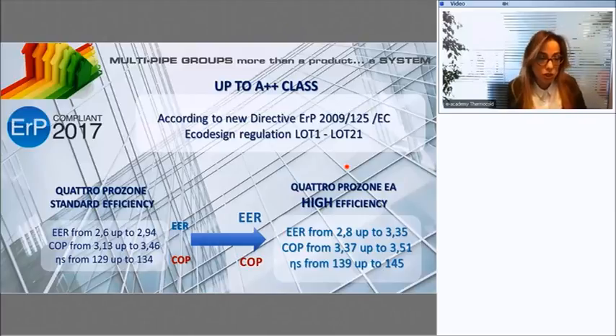As I was mentioning before, another driver of our redesign process was the eco-design regulation. According to the new eco-design regulation, all the heat pumps, and of course the multi-pipe is considered as a heat pump, must be compliant to certain levels of seasonal efficiency in heating mode. The eco-design regulation will be enforced starting from September 2017.